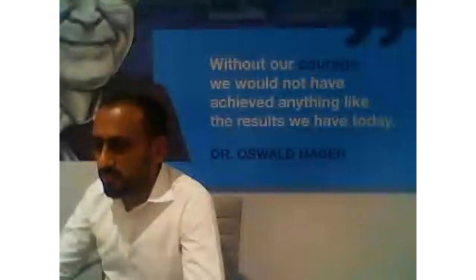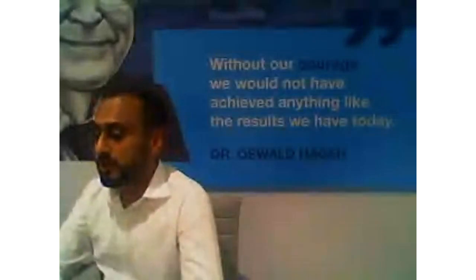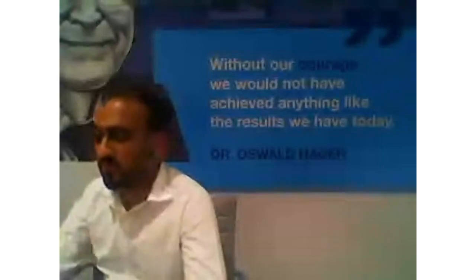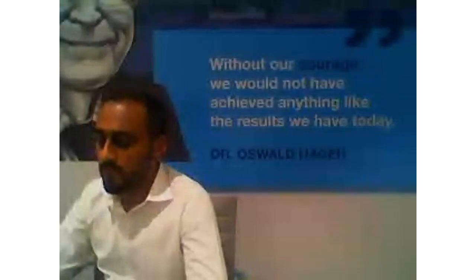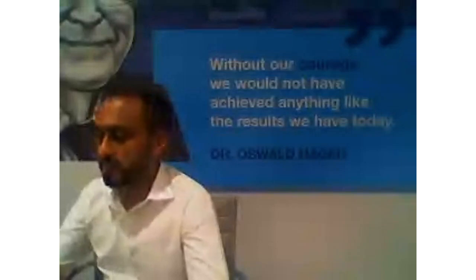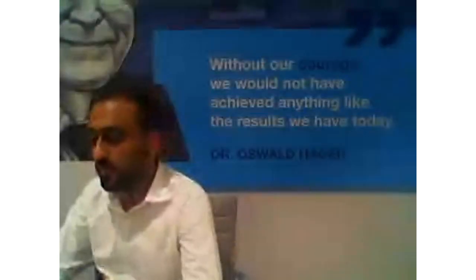So what is the major difference from ICU to ICS breakers? I believe you're asking about the different kinds of breaking capacities. So we have ultimate breaking capacity and we have service breaking capacity. ICS is the service breaking capacity. Generally, the service breaking capacity is a percentage of your ICU values, and in Hager we have a full range from 50% to 100% depending upon the type of breaker.